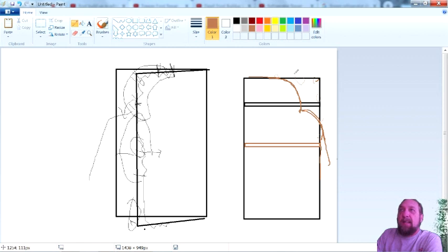So now I take the new gasket and I tuck it in from here to here. The rest is just hanging down and hanging in my way, but I just tighten up only a few screws. Now what I'll do is I'll take these screws loose, peel off this part of the gasket. Now this part of the gasket is going to be hanging like this.